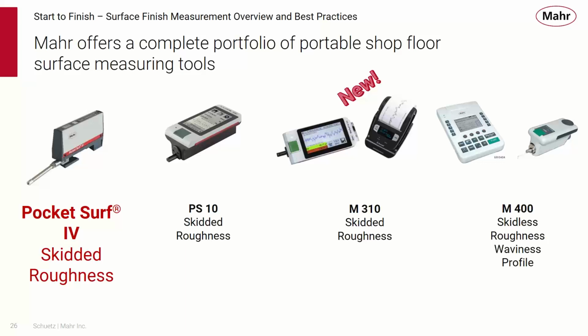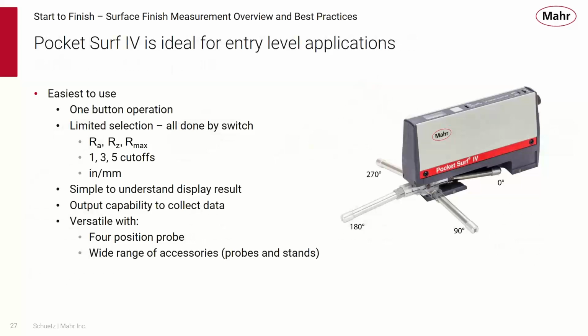So let's take a look at the PocketSurf 4 for skidded roughness. The PocketSurf 4 is ideal for an entry-level application of surface measurement. It's been around for nearly 35 years. It's probably the easiest to use portable surface gauge out there with its single one-button operation. It's simplistic in that it limits selection, all by switch of doing Ra, Rz, or Rmax. It has 3 cutoff length selections, and it can be metric. So it's simple to understand. It has a single display unit, which gives us the result. It has output capability for data collection, and it's extra versatile with its 4-position probe, pointed out here in the picture, and it has a wide range of accessories with its probes and different stands.